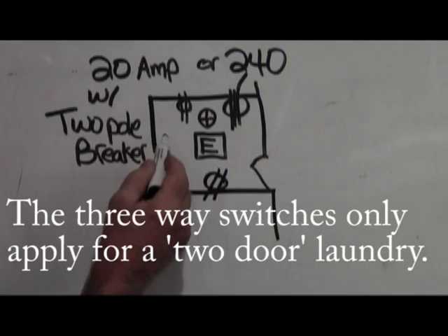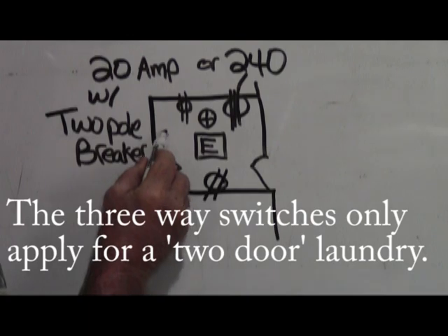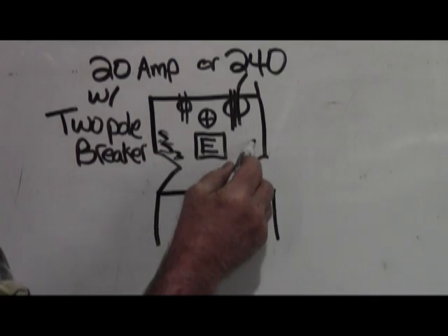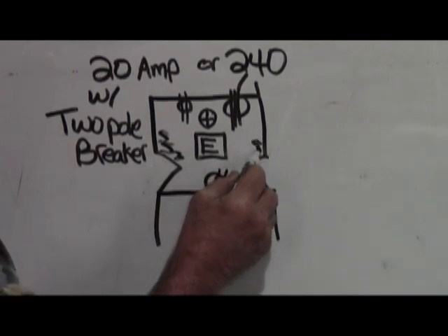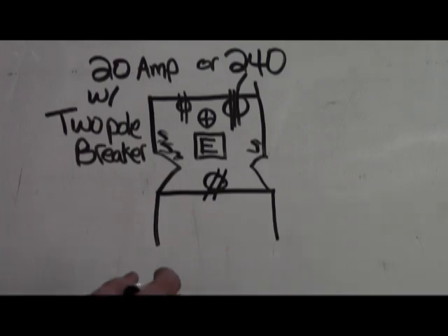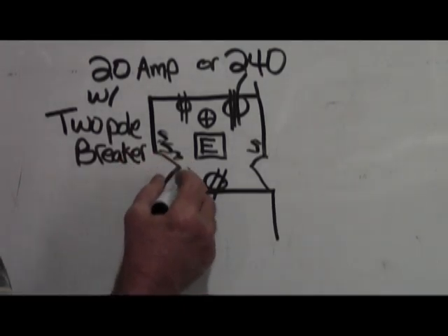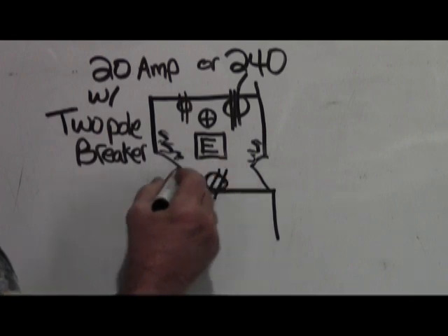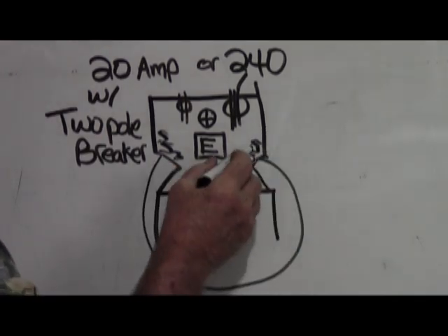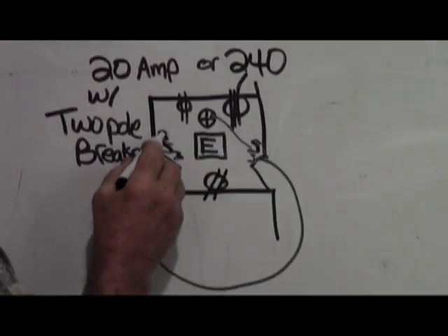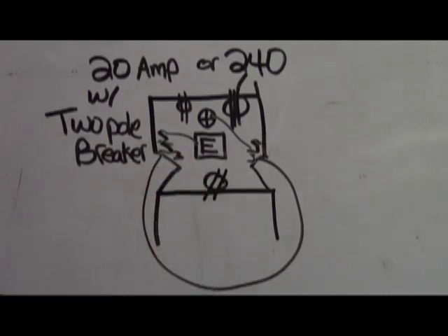If it has a light, it's going to have to be a 3-way, okay? Because this is over 6 feet wide. So that's switch 3 to switch 3, right, for the light, and then 1 switch goes to the exhaust fan.